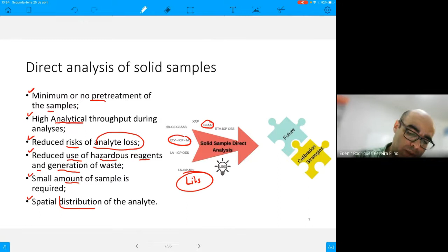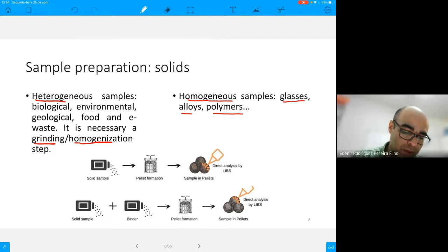And now LIBS can be in the team of several other analytical chemistry techniques, for example, graphite furnace, ETV, electrothermal vaporization, laser ablation with ICP-OES, or laser ablation with ICP-MS. Okay, how to prepare the samples, solid samples, for instance. We have several problems. For example, heterogeneous samples. In the majority of the cases, we need a grinding process in order to homogenize the sample. With homogeneous samples like glasses, alloys, polymers, we can present the sample directly to the instrument.